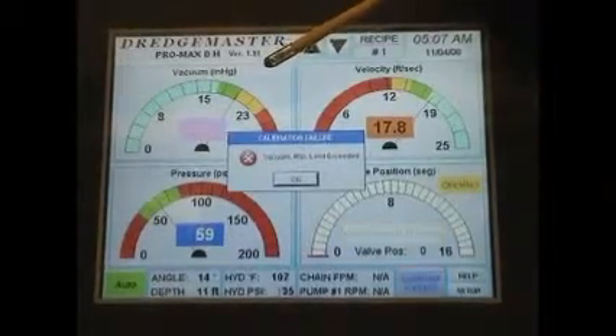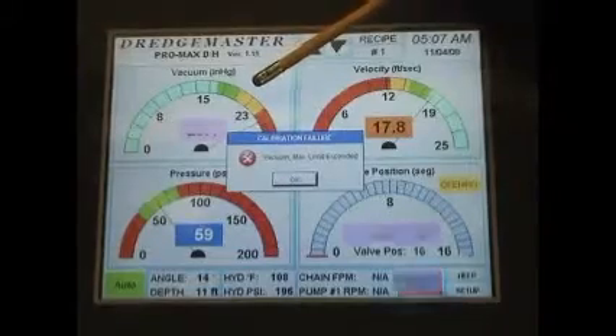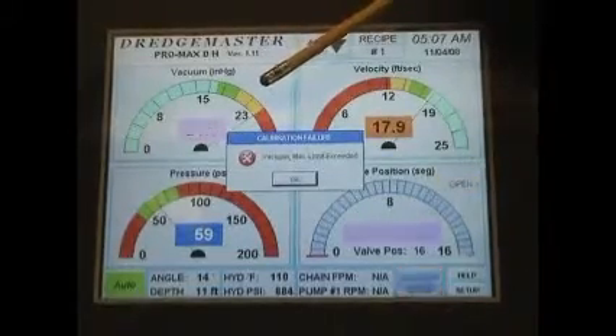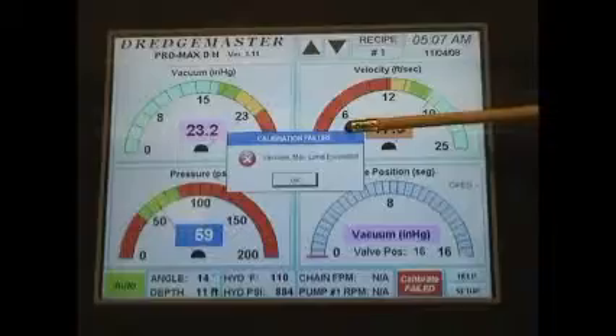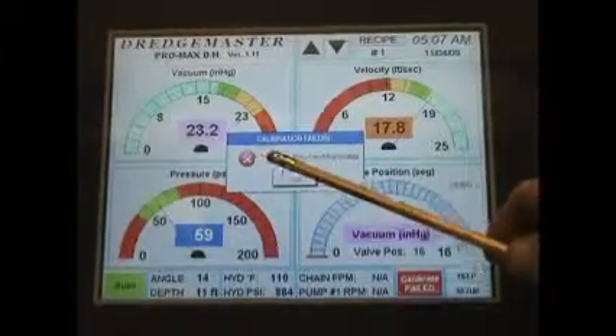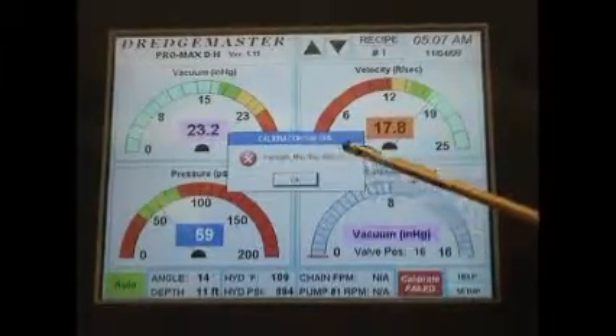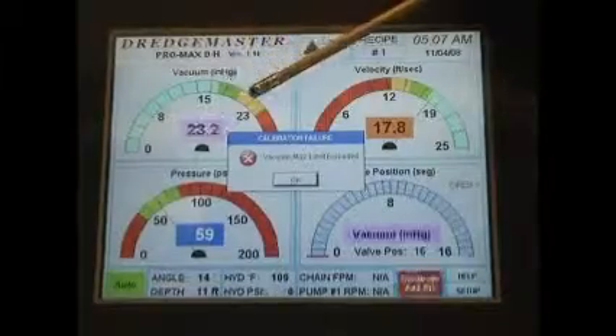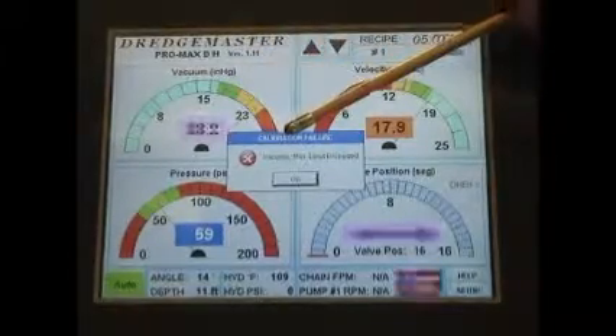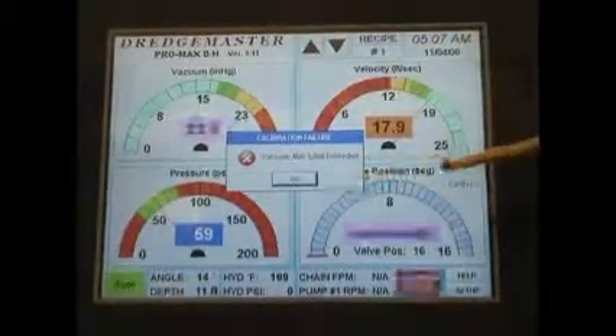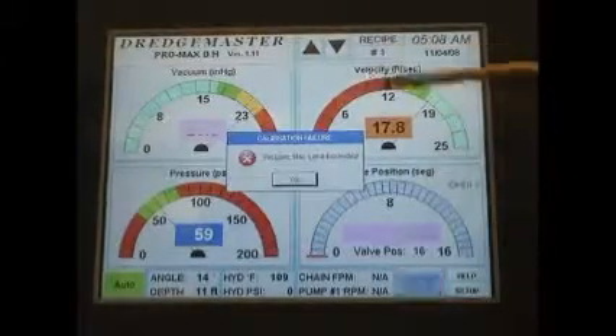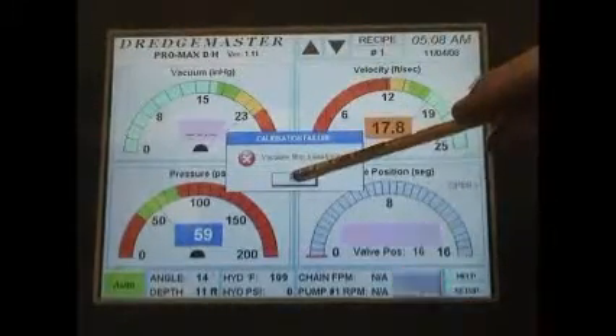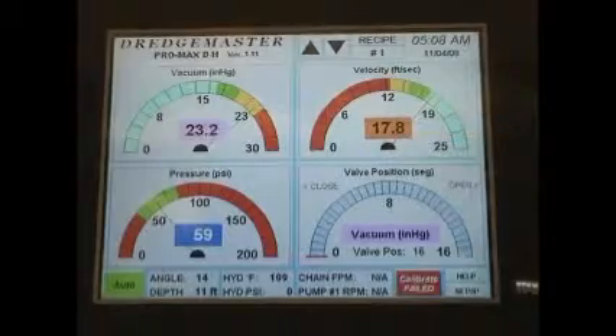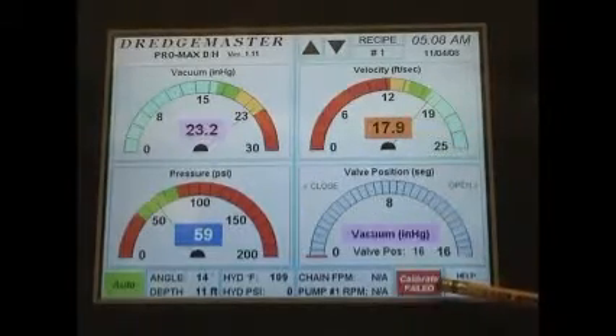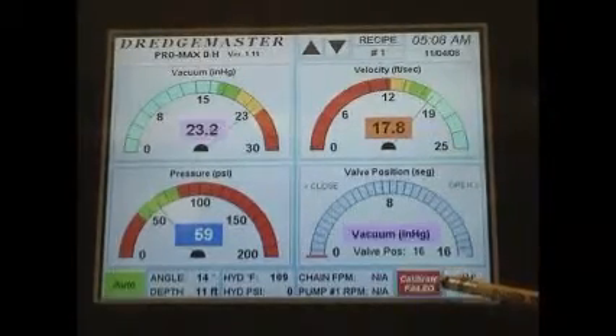Once the vacuum is in the yellow or the red zone, we get a message that says calibration failure. In other words, the vacuum maximum limit has exceeded. So once we got into that yellow zone or higher, our calibration process has stopped. We're going to say OK to this prompt right here. And now notice we have a calibration failure light blinking.